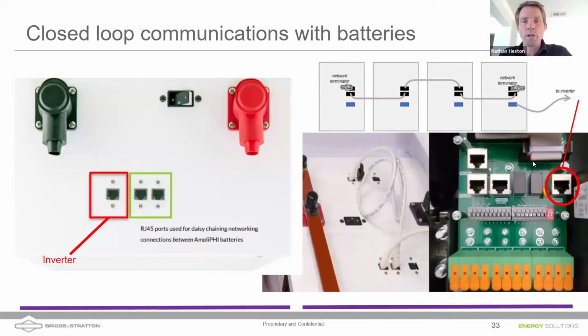I'm going to point out closed loop communications. I just talked about it, but with batteries. So if you're using any of our communicating batteries, you're going to want to make sure that you have a terminating resistor in a battery that has an empty CAN bus port. You never want to have a floating CAN bus port there. You need that resistor to let it know it's the end of the daisy chain. So you'll fill all the ports of those batteries, of the CAN bus sides of the batteries, those RJ45 ports. So don't throw out that bag that comes with the cable, even if you have your own. And so you'll have a terminating resistor like that. You go battery to battery, battery to battery. And then from that final battery stack, you would go to the inverter.